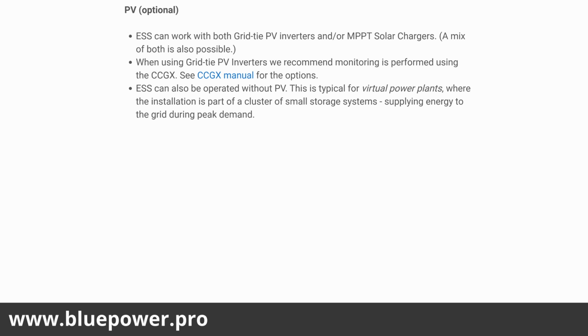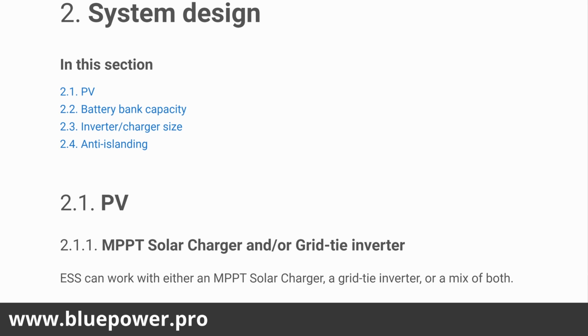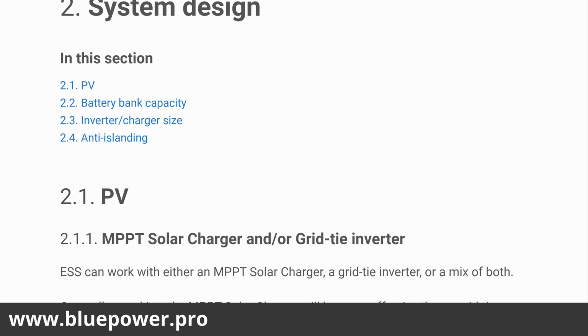This is essentially for virtual power plants where the installation is part of a cluster for peak demand shaving or that. So more specific use case scenarios. So generally, you're going to run your ESS system with solar power in the residential or commercial installation. That's just to utilize your PV consumption and self-consumption of the system. So here we've got system design. First section is the PV.